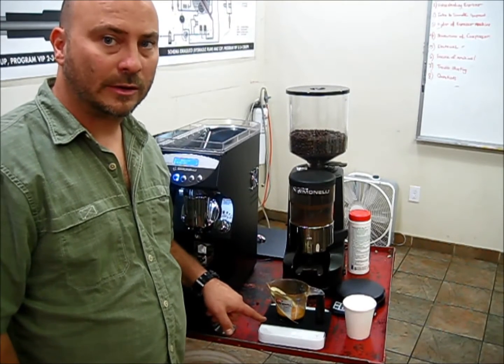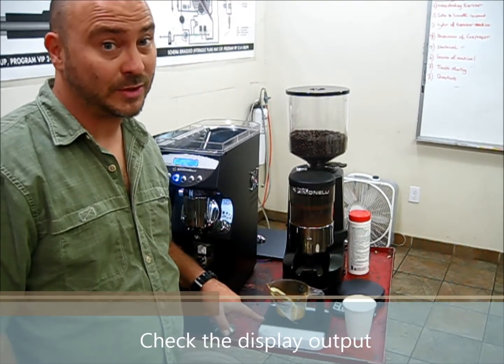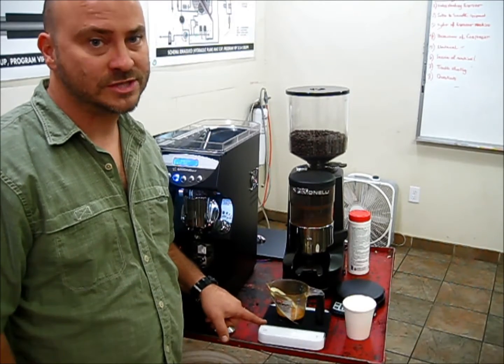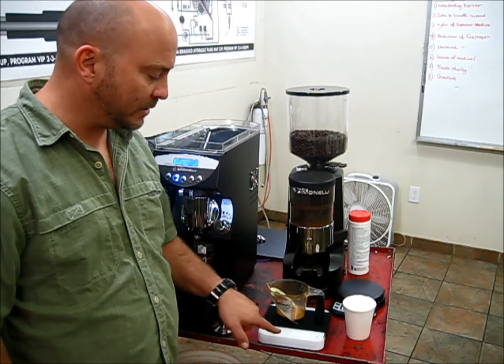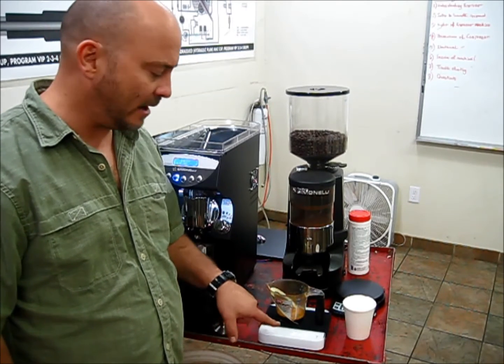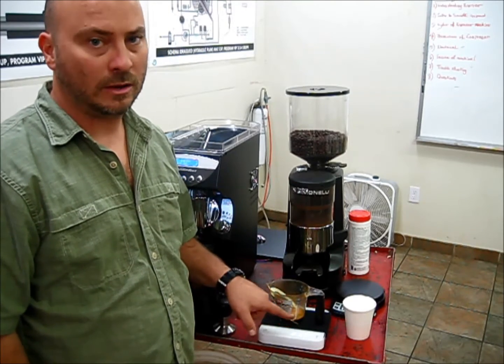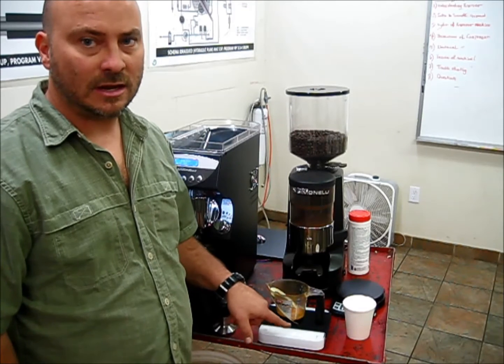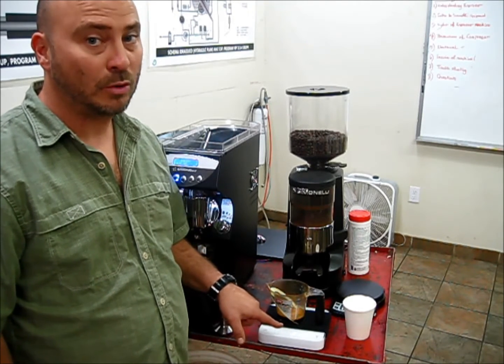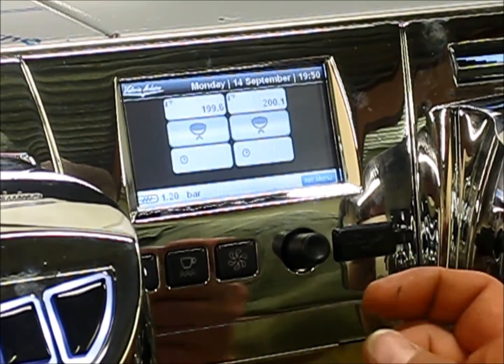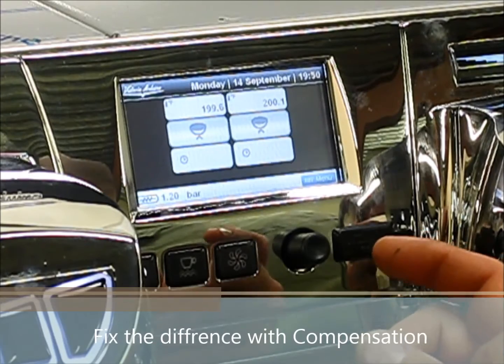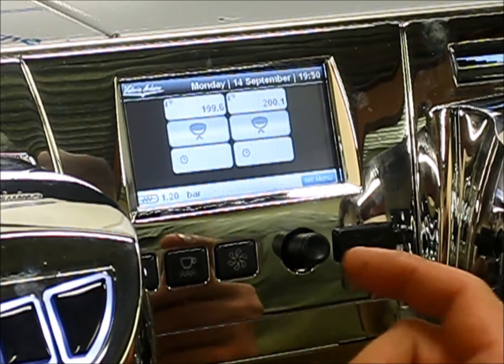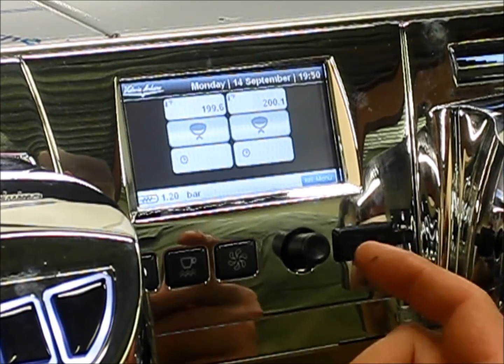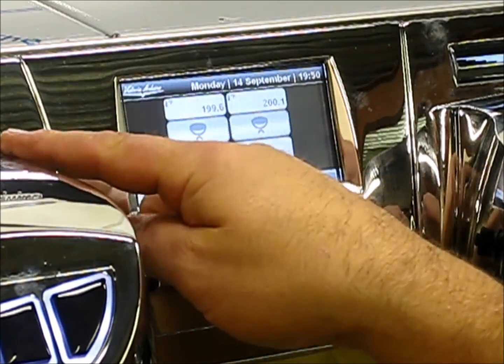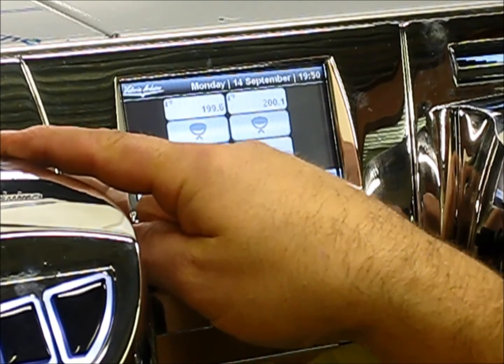So, as we've learned, our display output on the Black Eagle gravimetric was 32 grams. We come over to our controlled scale, in this case the Acaia, and we notice that the liquid quantity we pulled actually reads 31.1 grams. To fix this, we will access the programming on the gravimetric machine, a part of the menu of the Black Eagle gravimetric that allows us to do a compensation in weight. As you recall, the weight on the Acaia scale was not in line with what the Black Eagle was reading, so we have to compensate for that difference.